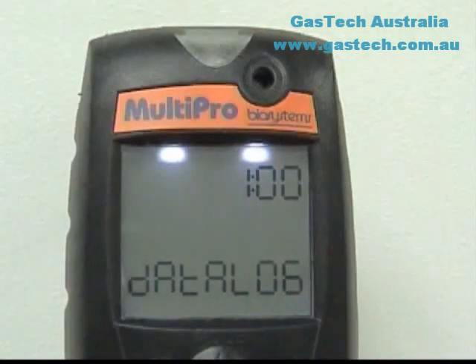If your Multipro includes the data logger upgrade, the current data sampling interval will be shown in minutes with the word data log. At the default data log sampling interval of 1 minute, the Multipro will store approximately 41 hours of data before it begins to write new data over the oldest data.